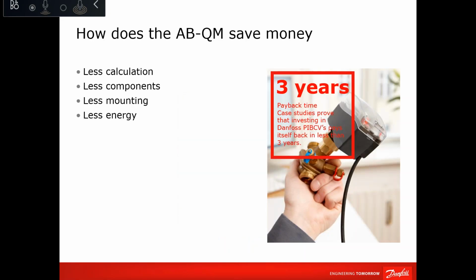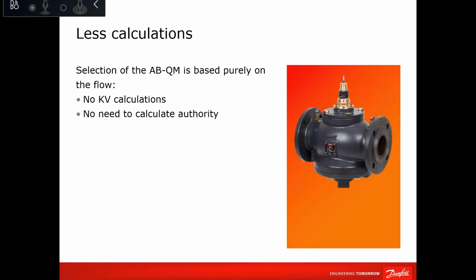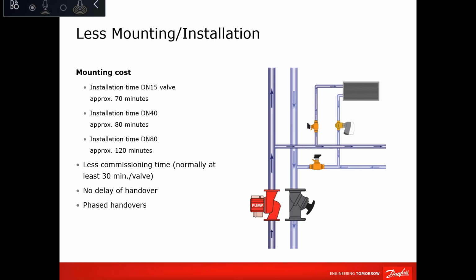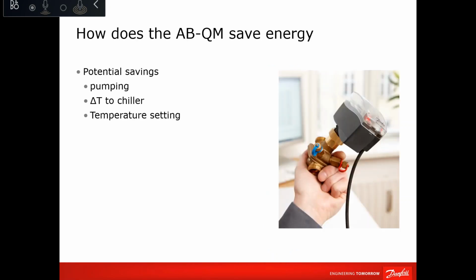So how do the valves save money? No calculation required, no Kv calculation, no authority. Mounting: if we are using PICV in your terminal unit, no need to use any balancing valve in the system. It's no more required because the PICV has its built-in automatic balancing function, which will do the job of a manual balancing valve. So every balancing valve in the system can be removed.